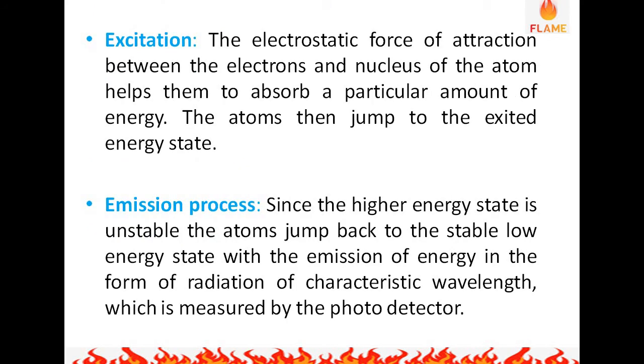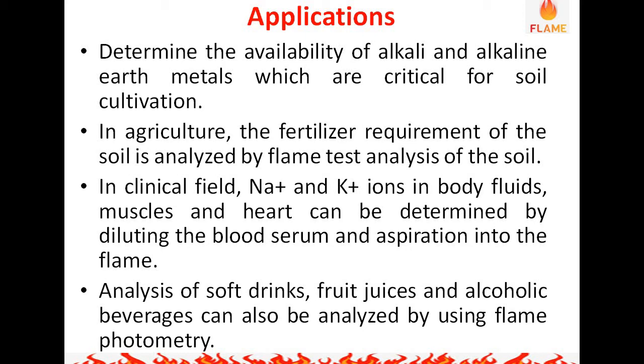The next important process is excitation. The electrostatic force of attraction between the electrons and the nucleus of the atom helps them to absorb a particular amount of energy. The atoms then jump to the excited energy state, and this process is known as excitation. Since the higher energy state is unstable, the atoms jump back to the stable low energy state with the emission of energy in the form of radiation of characteristic wavelength, which is measured by the photodetector — this process is known as emission.